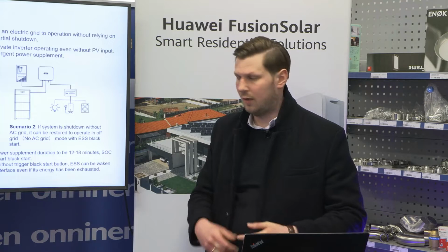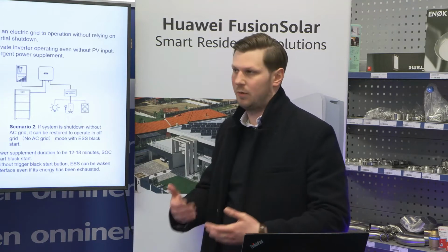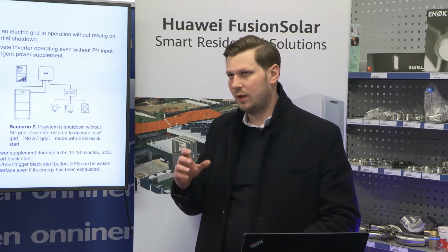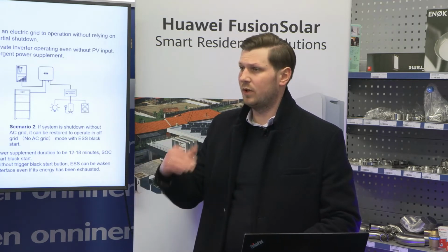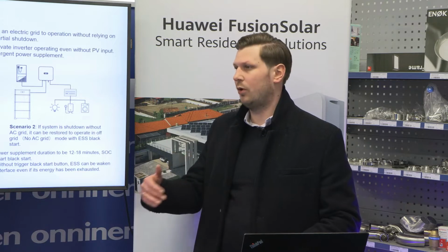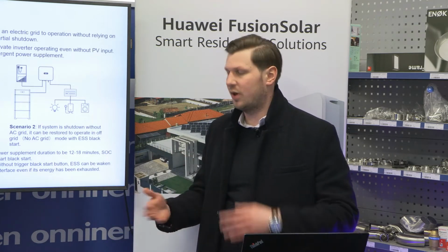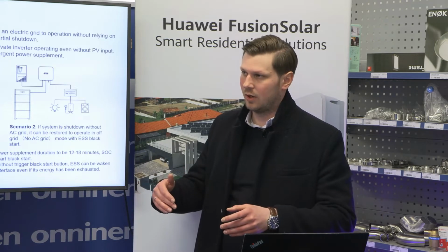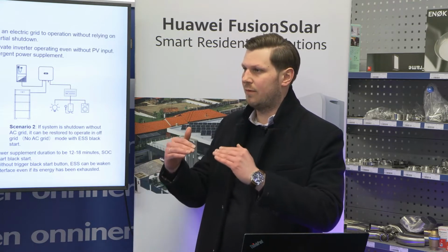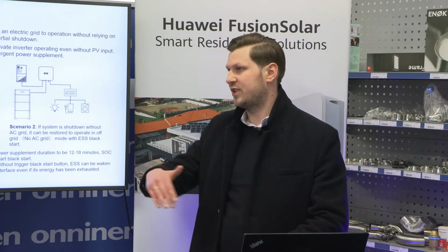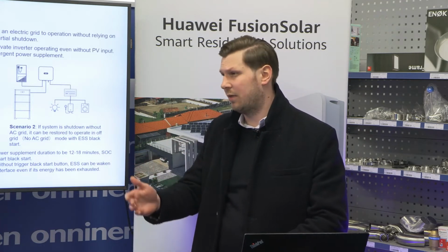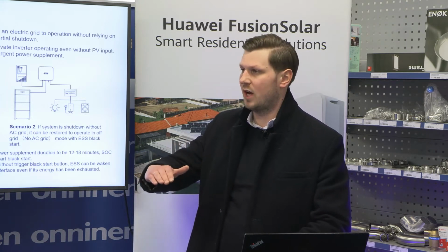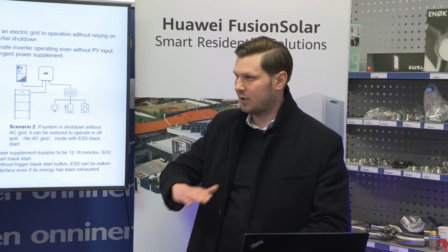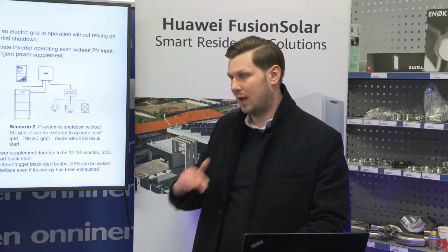Can we discharge to 100%? Yes, though it will of course affect the lifetime of the battery. The Luna battery packs don't only have 5 kilowatt hours of capacity - there's always some spare capacity, really about 5.15 kilowatt hours. So even if you set your storage to discharge to 0%, it's not harmful to the equipment at all, under one condition: you just don't keep the system at zero level for a very long time, because it has some self-discharge factor, around 2% per month. So if you keep it at zero for a very long time, the battery might really discharge to the relative zero, and that might shorten the lifetime of the whole system.